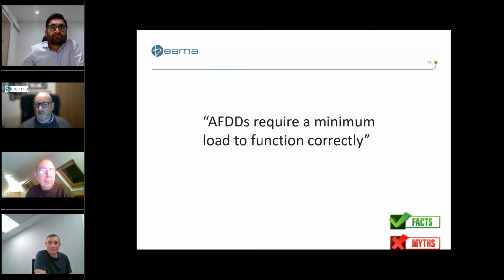Any other comments? For series arc faults, you might think, will I get 2.5 amps, so do I need to protect the circuit? But there's also the issue of parallel arc faults, which can be well over 2.5 amps - quite probable since you'd have a relatively low current load. So it's important to realise there is a load current limit, but also that it's not just one type of arcing; it can be series or parallel.